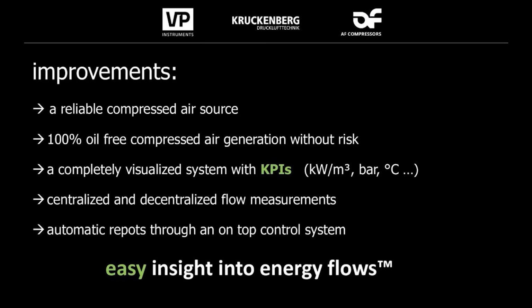In the compressed air rooms, with the change of technology, when they want to make the step from oil lubricated or dry two-stage screw compressors to piston compressors, you have an optimization potential of 15%. But this potential is also not common knowledge. It's still a big advantage in the consultation, because piston compressors were old-fashioned for a long time, and this technology has been optimized for many years, but it's just getting a revival. Because nowadays you can get piston compressors which can be regulated like a VSD-driven screw compressor, but with a much more durable pneumatic solution inside. So you are competitive.